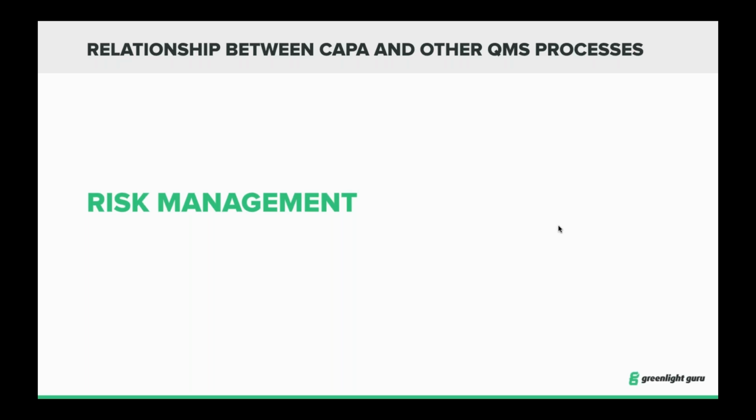The other concept that was introduced to us in 13485:2016 is this notion of a risk-based quality management system and risk-based approaches. And I think that's really important when deciding whether or not we should issue a CAPA: applying a risk-based decision-making process. And then if you have a CAPA, what you do about it and whether or not further action is required. Risk should really be the center of that entire decision-making process about what to do, when to do it, how to do it, and those sorts of things.